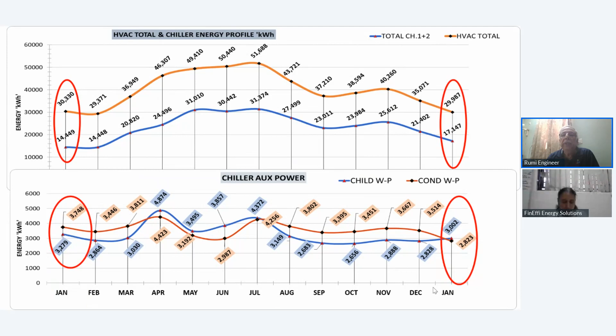The second analytics here - the beauty over here is, come April and May, definitely summer is coming, and you see the ulta bell curve, the inverted bell curve. So from 30,000, the overall consumption has increased to 46,000. From the chiller, it has gone from 14,000 to 24,000. Fine, acceptable, because that is expected.